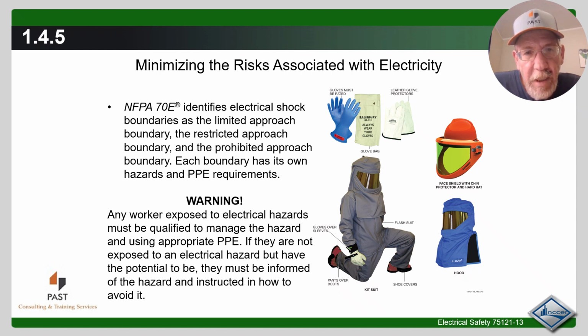The warning is indicating that any worker who is exposed to electrical hazards must be qualified to manage the hazard and use appropriate PPE. If they are not exposed to an electrical hazard but have the potential to be, they still must be informed of the hazards and instructed on how to avoid them. In 2015, NFPA did remove the prohibited approach boundary from the NFPA 70E standard for electrical safety in the workplace.